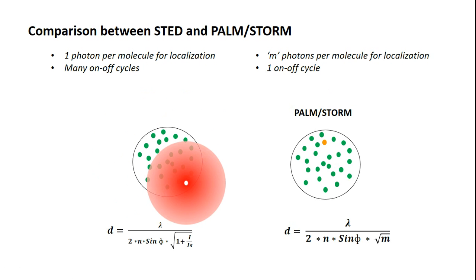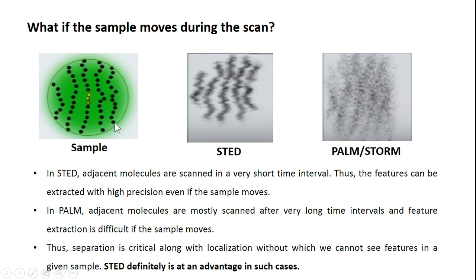In PALM/STORM, when one molecule is active all others are depleted. Another key advantage of STED is that when the sample moves during scanning, adjacent molecules are scanned in very short time intervals so features can be extracted with high precision. In PALM/STORM, adjacent molecules are mostly scanned after very long time intervals due to random excitation, making feature extraction more difficult. Separation accuracy is critical alongside localization precision, and STED is advantageous in such cases.